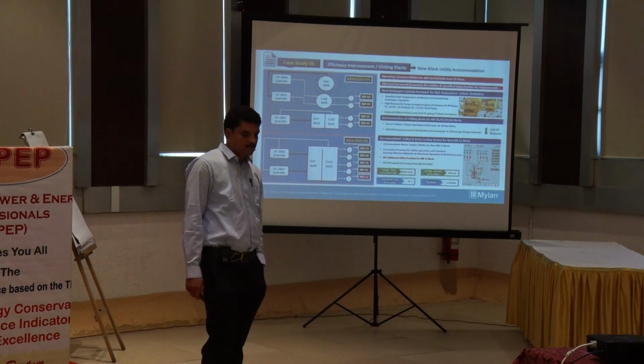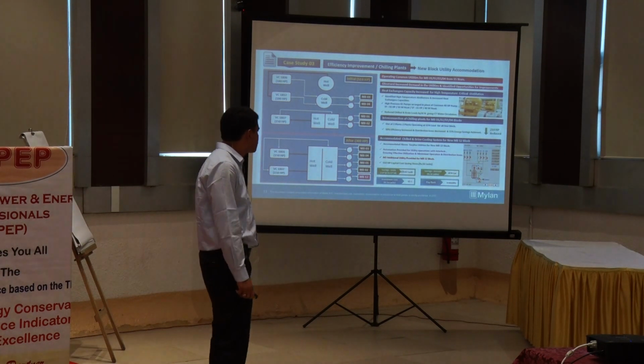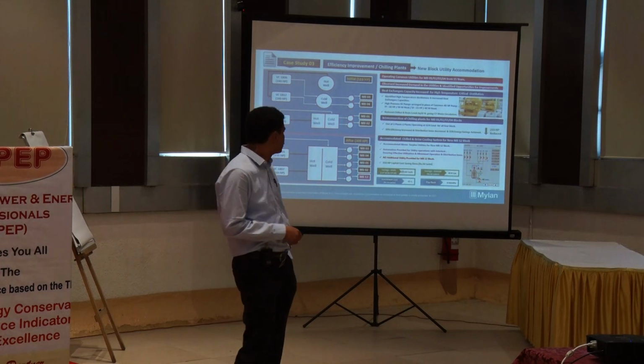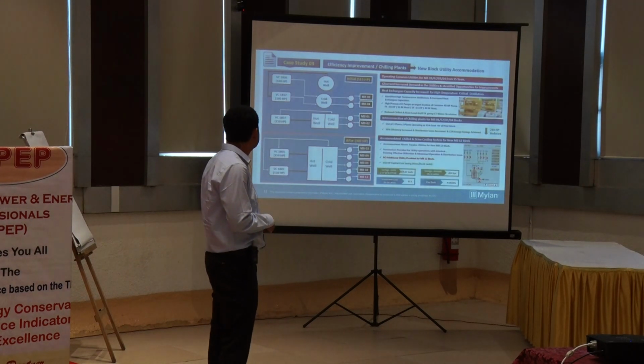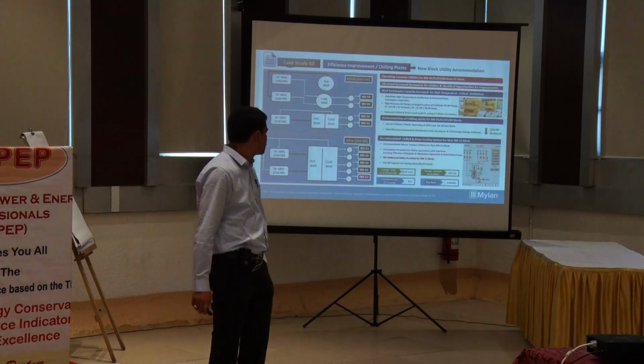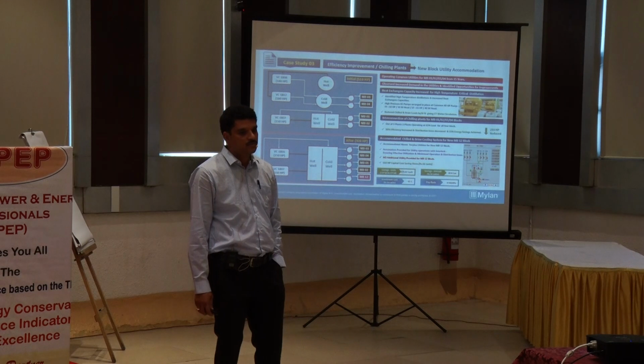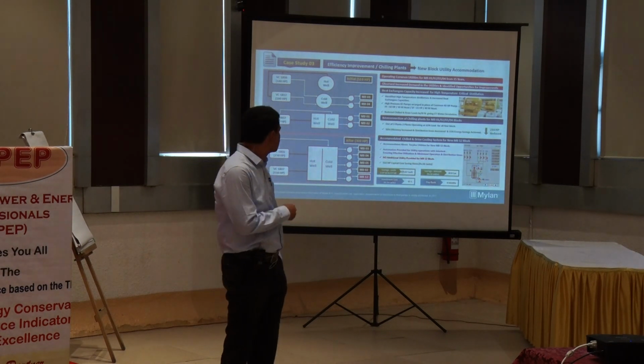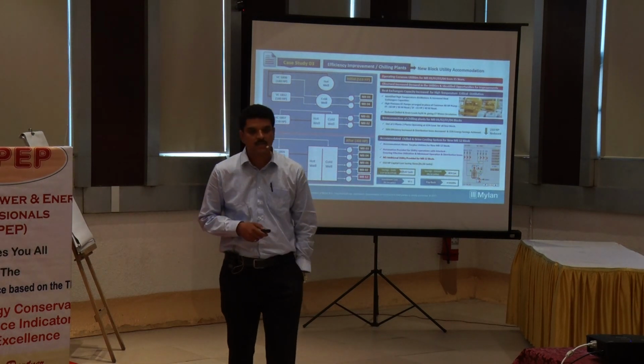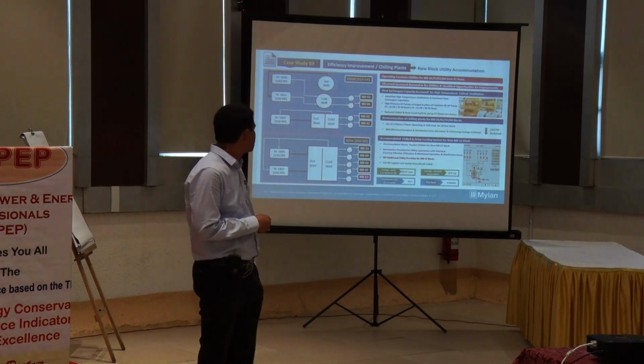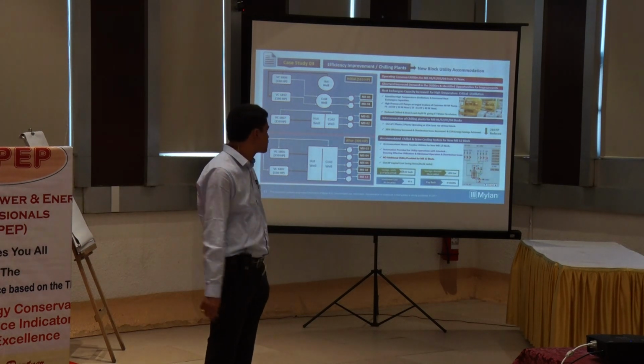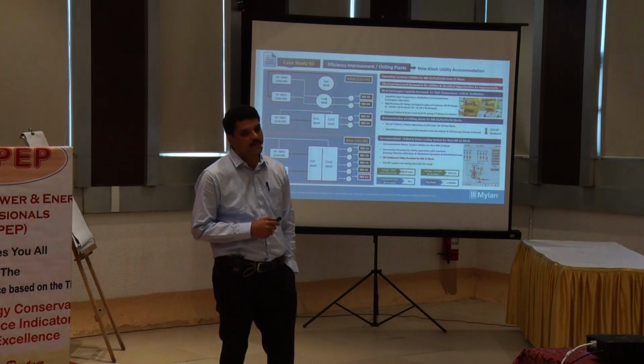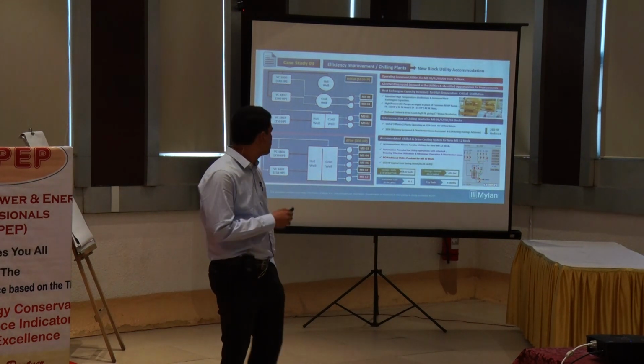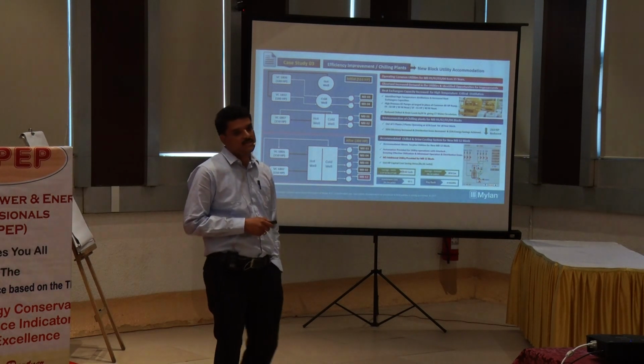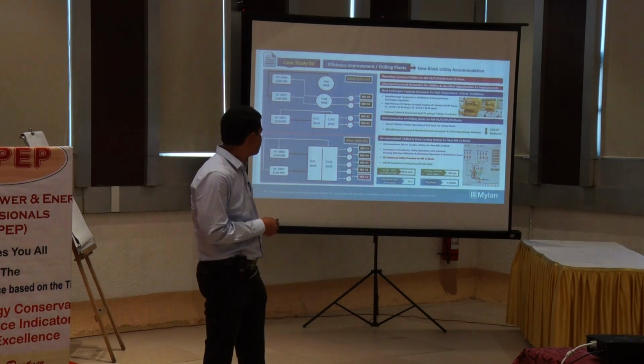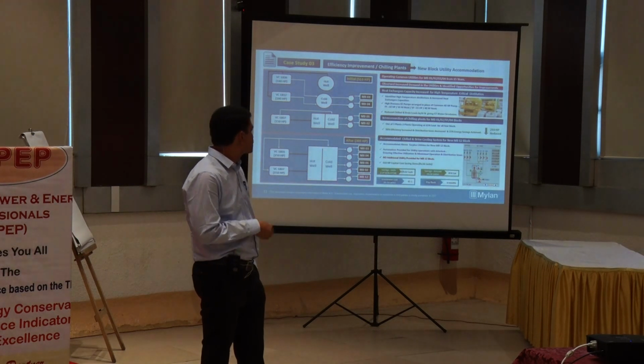This is one of important and high potential case study. The existing system efficiency improvement. So our 4 manufacturing blocks connected to common utilities. And later on, we observed a huge utility demand. To overcome that, we have reviewed everything through brainstorming sessions, and we found that there is a possibility of improving distribution system. So we have installed floor-wise CT water pipelines and high-efficiency CT water pumps. And wherever required, we have enhanced our heat exchanger capacities. With that, more than 50% of the load was reduced from chilled water, chilled brine to CT water.